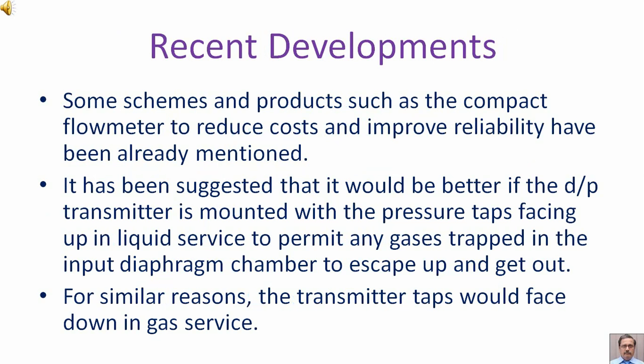It has been suggested that it would be better if the DP transmitter is mounted with the pressure taps facing up in liquid service to permit any gases trapped in the input diaphragm chamber to escape up and get out. For similar reasons, the transmitter taps would face down in gas service.